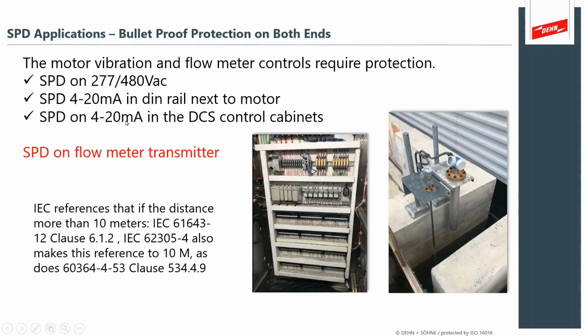What's really important is to pay attention to the 4 to 20 milliamp control cabinets and make sure that you've paid attention to that shield and you watch for distances greater than 10 meters where you'll know you'll want protection. What's interesting about some of these applications is that they're mounted on steel pedestals, but the steel isn't bonded to anything. So essentially this looks earth, but it's not earth. It's literally floating over this water control panel. So that's really important to pay attention to how the ground wire was mounted and installed on these types of applications. So you're avoiding weird ground loops or secondary loops.